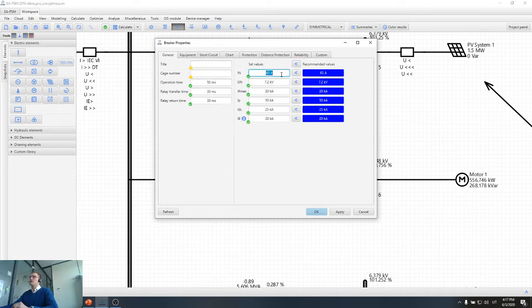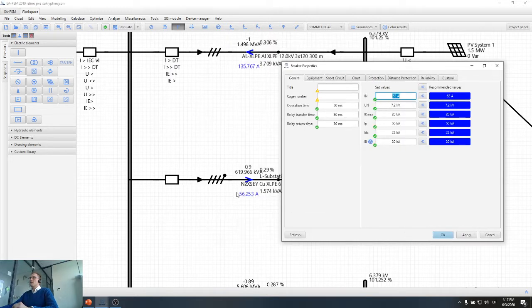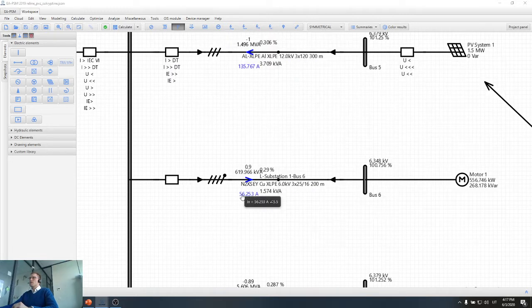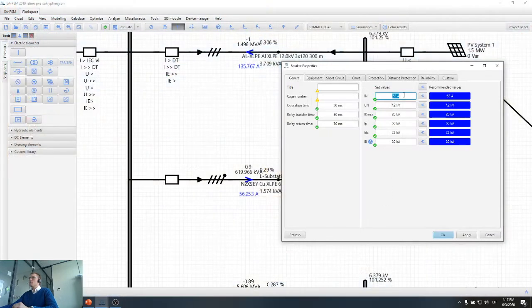So for example, nominal current should be 63 amps. This is bigger than normal current of the motor, which is good. So our breaker should have bigger nominal current. Voltage level is 7.2 kilovolt. So you see that our network voltage is 6.3 kilovolts. However, nominal voltage of the circuit breaker is bigger.